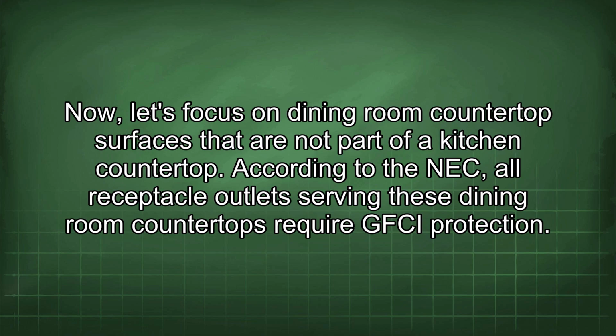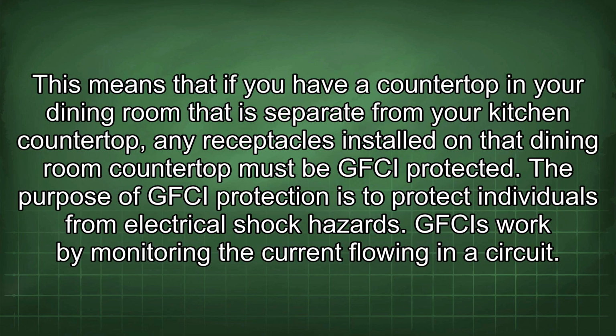Now let's focus on dining room countertop surfaces that are not part of a kitchen countertop. According to the NEC, all receptacle outlets serving these dining room countertops require GFCI protection. This means that if you have a countertop in your dining room that is separate from your kitchen countertop, any receptacles installed on that dining room countertop must be GFCI protected.